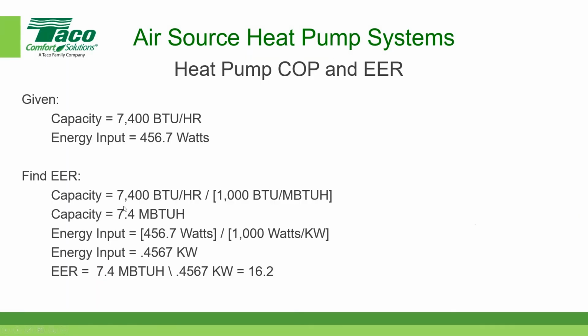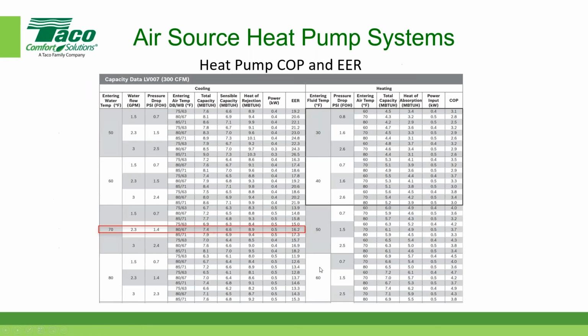Okay, so I'm using 456.7, or 0.4567. They rounded it off in the chart to 0.5, but if you do the calculation, it comes out to 16.2, and you can see right there the EER is 16.2. So only in America do they use this silly value of 16.2 for the EER. I don't know. Maybe they just like bigger numbers to make it sound bigger.